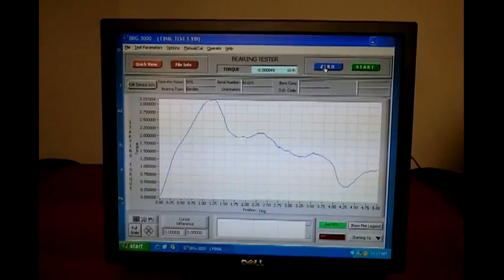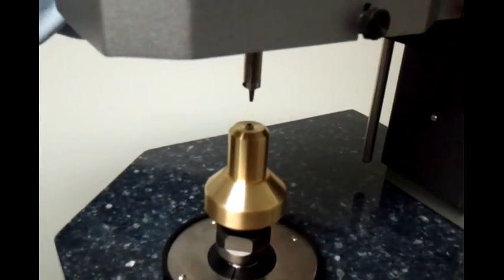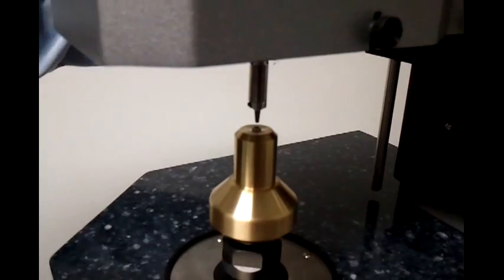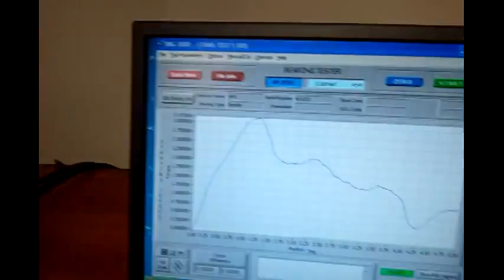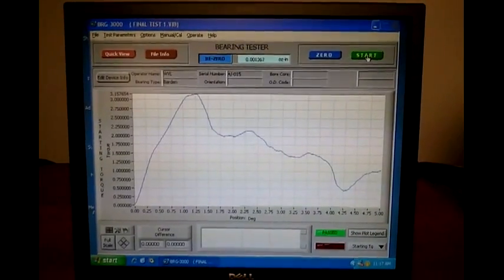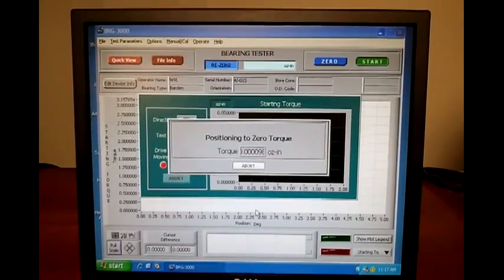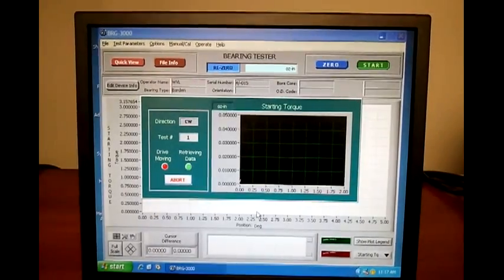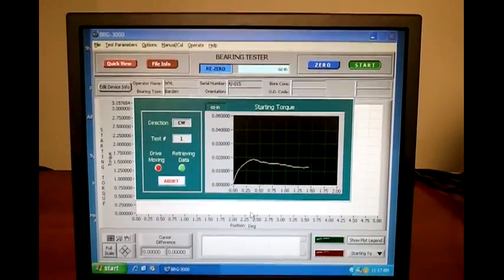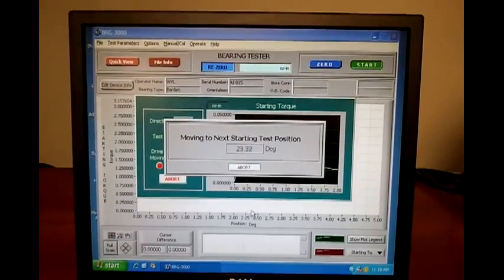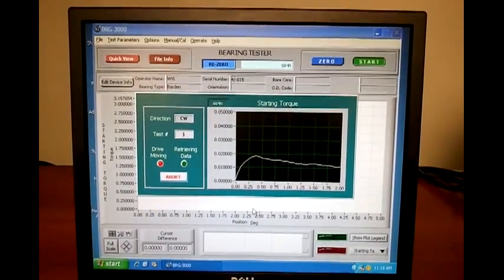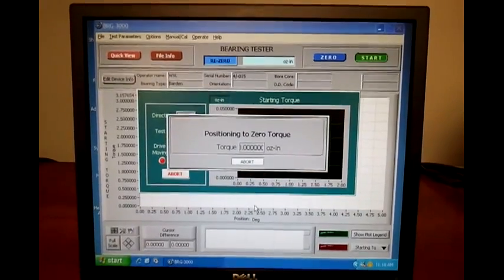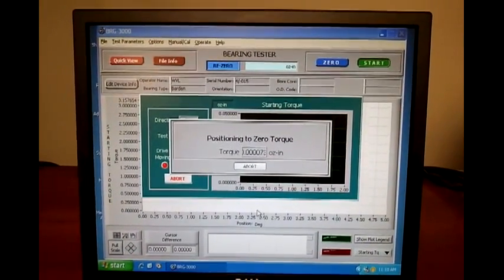So we will go over to the tooling and engage the transducer into the upper fixture. Go back to the screen and press the start button, at which point the transducer positions itself to zero and then performs the first test. Now it is going to index 90 degrees. It will find zero again and perform another starting torque test.